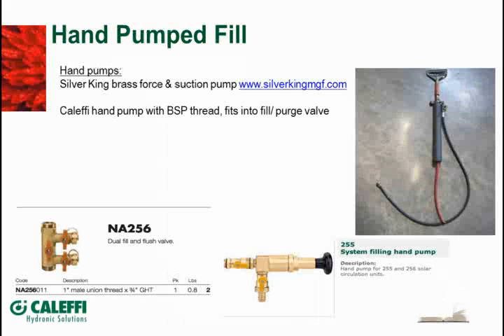A couple different pumps that I've got that I've used over the years. These are little hand pumps. Now, if you have a small system and you're just putting a couple gallons, maybe up to 5 or 10 gallons of fluid in the system, you can do that with a hand pump. You don't need to buy a big, motorized pump to do that.